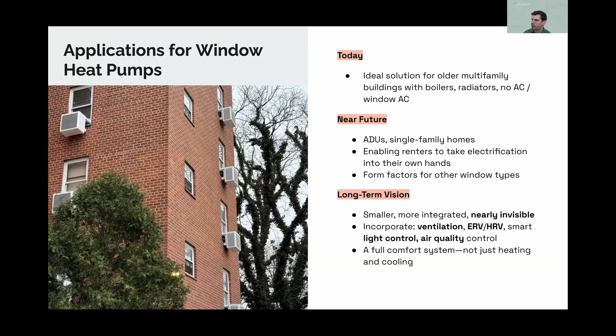Getting a little more technical, the features of these and how you practically make sure these projects go well, you've got to think about the entire building and the entire system. Obviously, these systems are being used to replace heating systems in very cold winters, and so you have to do something with condensate. You can drip water in a cooling system in the summer. It's an annoyance, but we live with it. If it's below freezing out, those drips would turn into icicles or ice puddles. So you either need a freeze-proof condensate line, which is a complex install and adds more cost to the install.